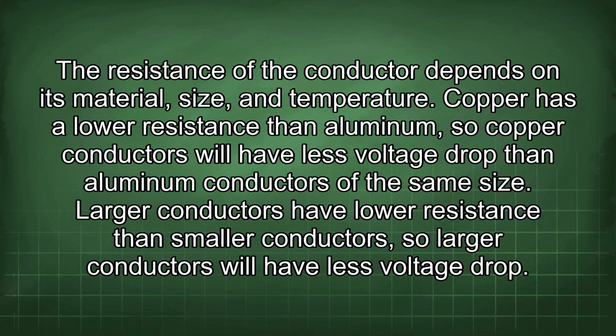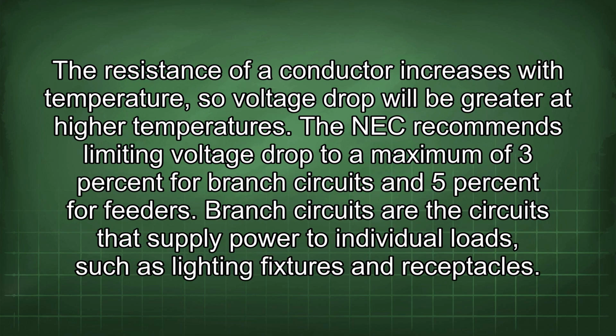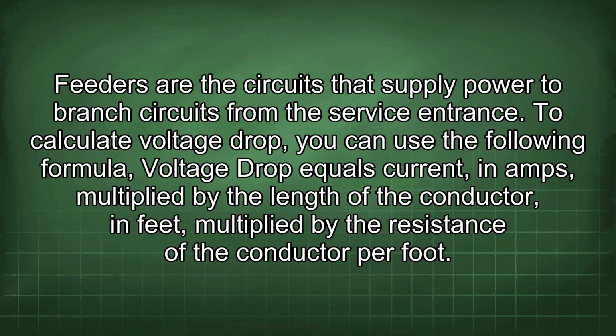Copper has a lower resistance than aluminum, so copper conductors will have less voltage drop than aluminum conductors of the same size. Larger conductors have lower resistance than smaller conductors, so larger conductors will have less voltage drop. The resistance of a conductor increases with temperature, so voltage drop will be greater at higher temperatures. The NEC recommends limiting voltage drop to a maximum of 3% for branch circuits and 5% for feeders. Branch circuits are the circuits that supply power to individual loads, such as lighting fixtures and receptacles. Feeders are the circuits that supply power to branch circuits from the service entrance.